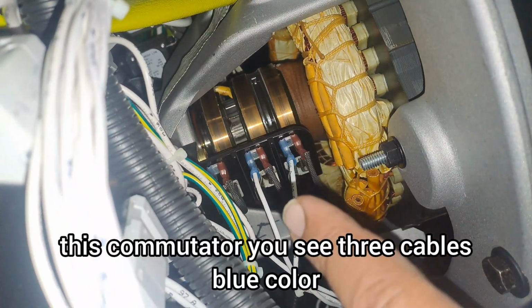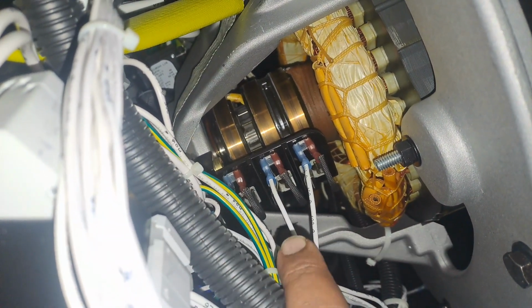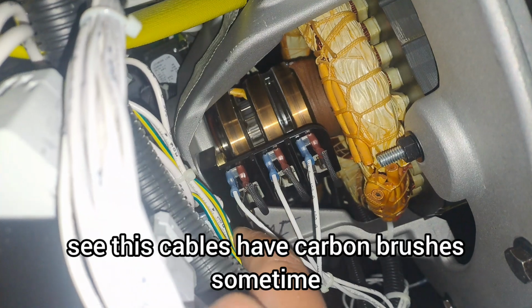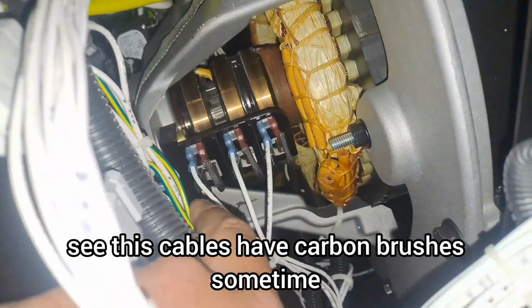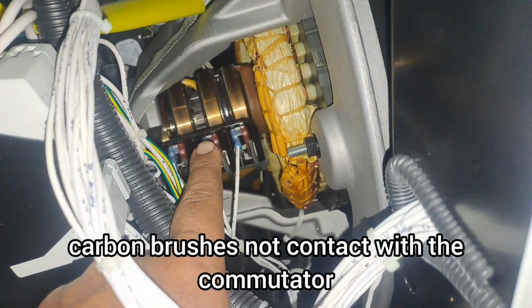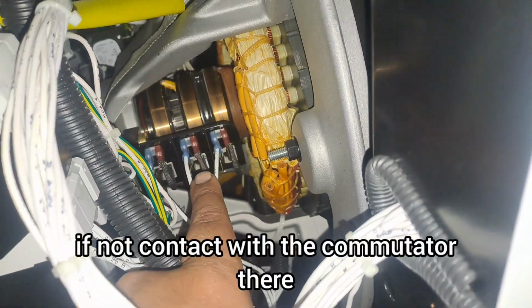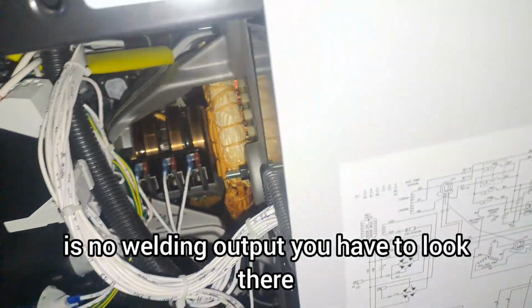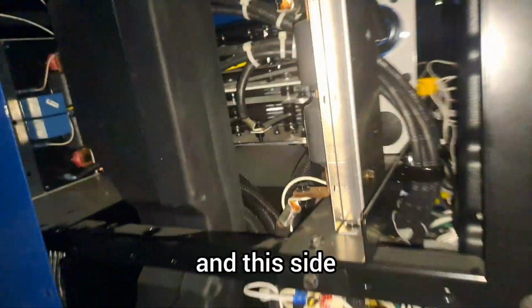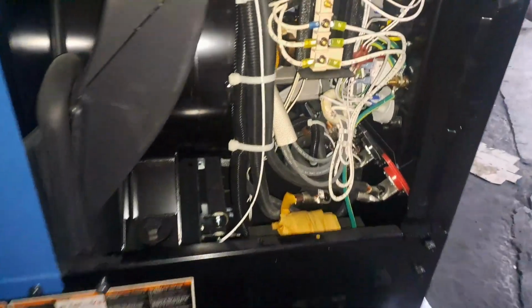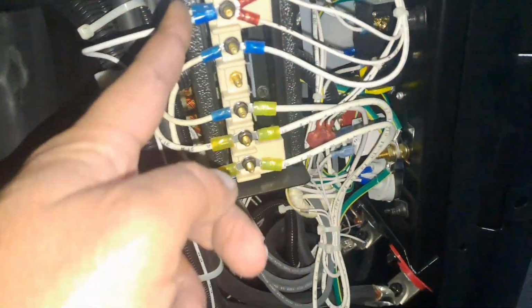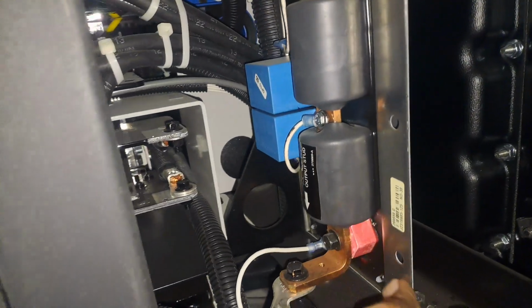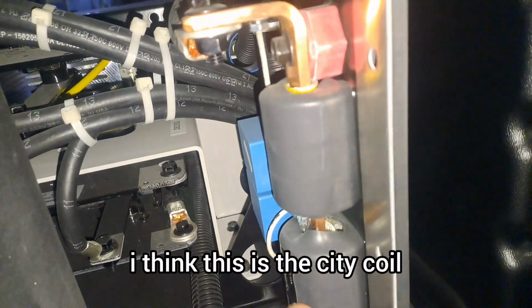This commutator, you see 3 cables, blue color. See, these cables have carbon brushes. Sometimes the carbon brushes do not contact the commutator. If they do not contact the commutator, there is no welding output. You have to look there. And this side, this plate is for 110 and 220 voltage. And here is this CT coil. I think this is the CT coil. Also there.